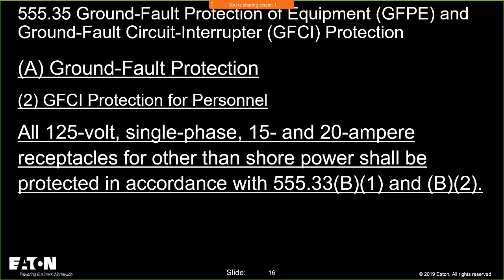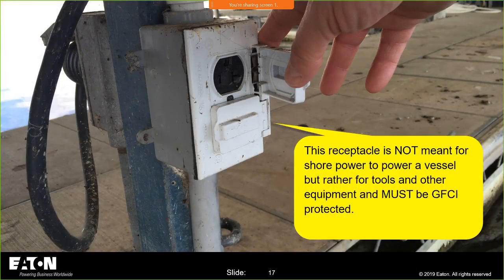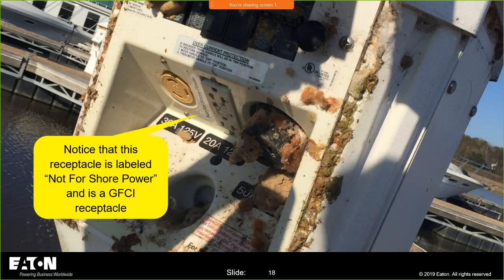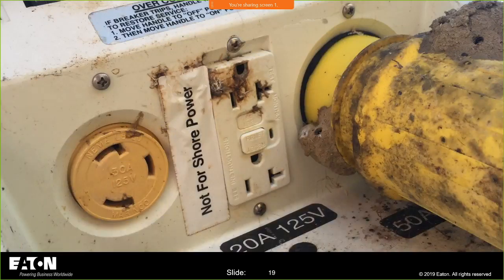And you have 15 and 20 amp GFCI people protection on anything you're going to be plugging into that's not for use as shore power. You'll see even on these pedestals, notes that say specifically not for use, not for shore power. So that's a GFCI receptacle there, but the other two, since they're for shore power, will have to be protected by a circuit breaker either in that pedestal or somewhere upstream feeding it—that's ground fault protection of equipment, GFPE, 30 milliamps.